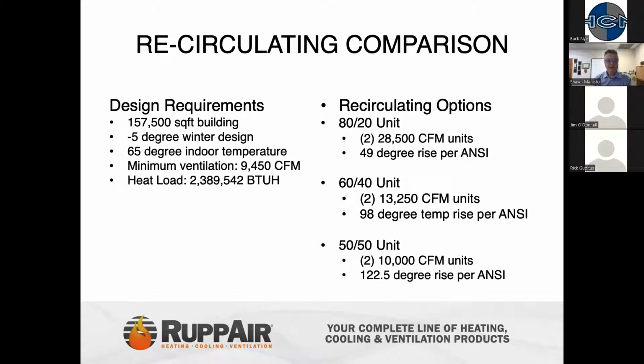This puts the illustrations side by side. This design building here is going to be 160,000 square feet. Starting out at -5 degrees, want to maintain 65 degrees. So we've already run this through our heat calculations and know what we have for a heat load. Traditionally, in the old 80/20 style systems, we need to have two 28,500 CFM units.